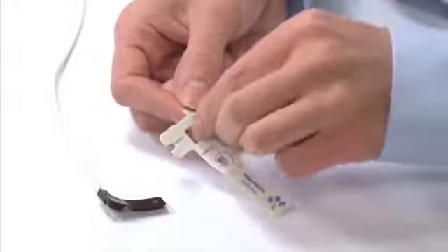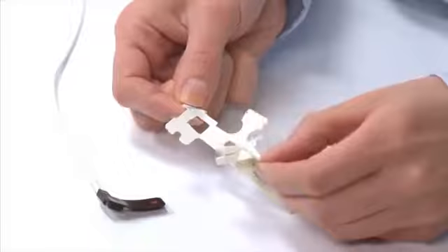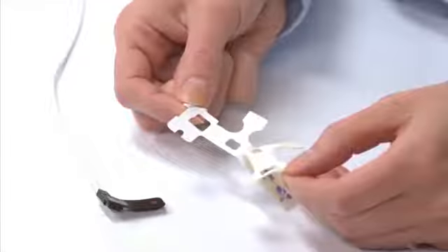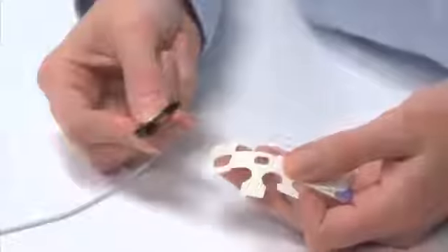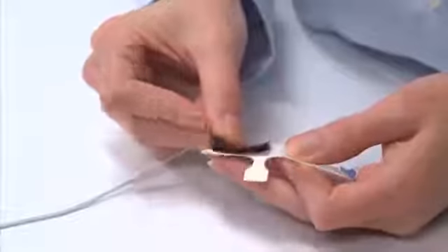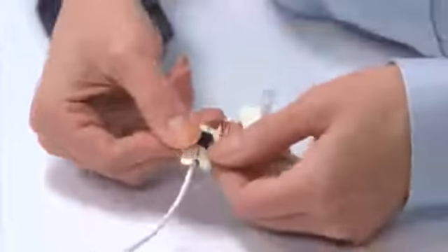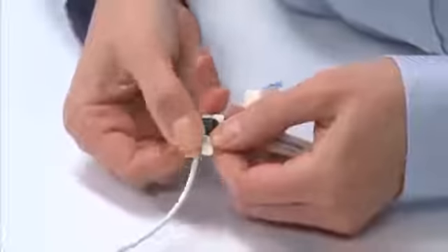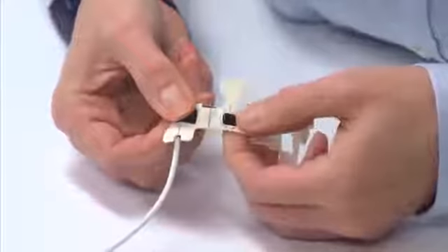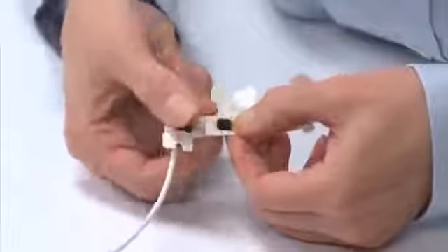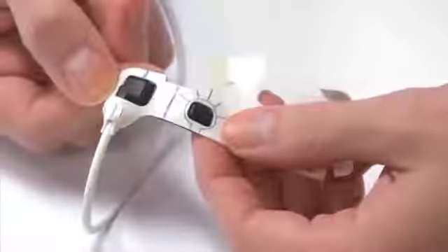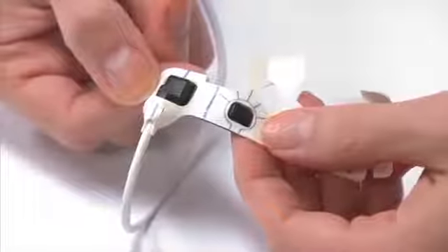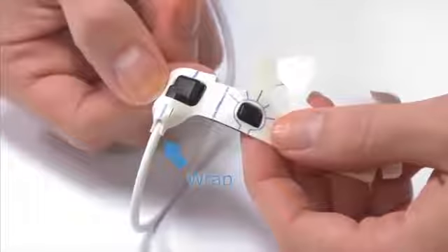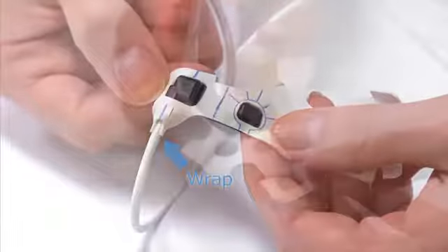Partially peel back the adhesive backing tab on the FlexiWrap so the sensor area adhesive is exposed. Align the sensor emitter and detector skin contacting side up to fit in the cutouts on the wrap. Then, gently press the sensor into place on the wrap. The cable should extend beyond the wrap supported by the adhesive and tab on the wrap. Remove the adhesive backing from the rest of the wrap.